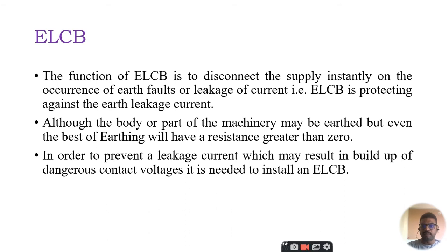Our next component is ELCB, that is earth leakage circuit breaker. The common problem found in MCB is that it will just cut the phase, it will not cut the neutral. The function of ELCB is to disconnect the supply in case of earth fault. If my conductor is connected with the ground, then it is earth fault or leakage current. ELCB protects against earth leakage current. Although the body or part of machinery may be earthed, even the best earthing will have resistance greater than zero. To prevent leakage current which may result in buildup of dangerous voltage, ELCB needs to be installed.